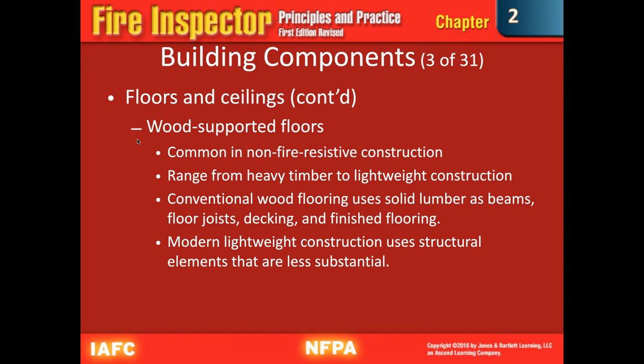These areas sometimes can contain electrical or telephone wiring, heating, ventilation, and air conditioning ducts. Plumbing, fire sprinkler pipes will run through here. If this space is not subdivided by fire-resistant partitions or protected by automatic sprinklers, the fire can get through here really quickly. That's one of the biggest issues about it. And again, usually when something is built, it's built to code. It's when you start renovating and adding things in, that's when you start messing with the building's design as far as fire prevention goes.